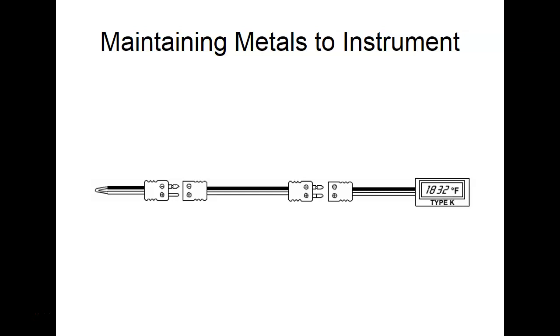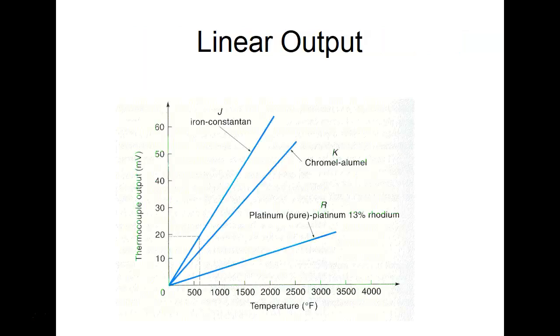It was the turbine inlet temperature that we screwed around with, and it must have had 50 thermocouples around the output of that thing, and they were all hooked in series. So what does that mean? The voltages add, each one of them. I don't know what voltages we got, and you can see these guys are really linear, right? Linear means they vary their output in proportion to the temperature. So these guys are pretty accurate, and they cover a real wide range of temperature measurements.